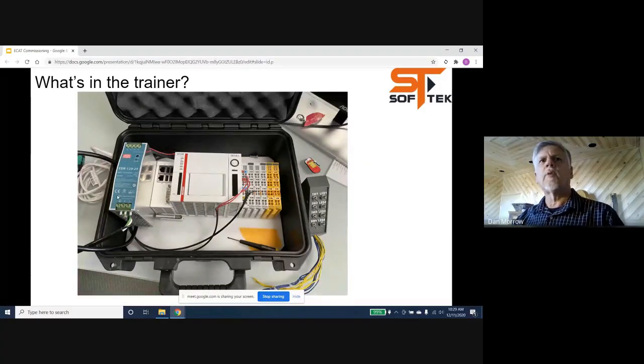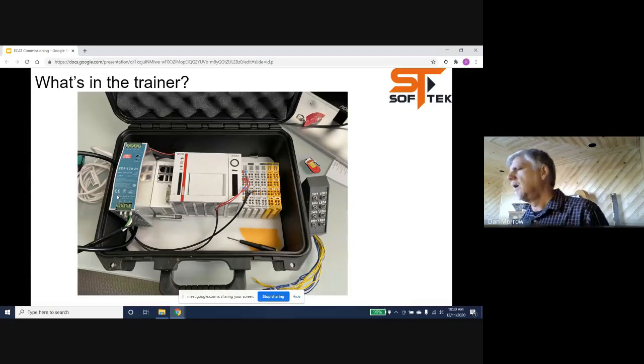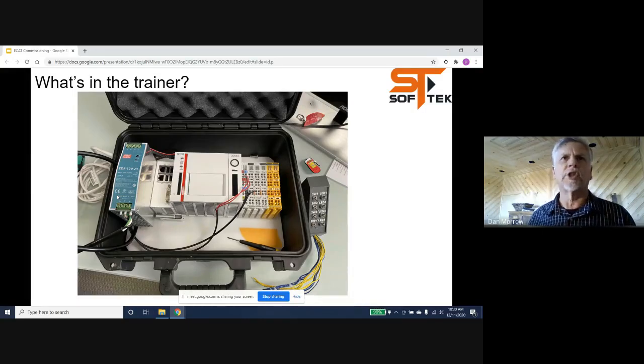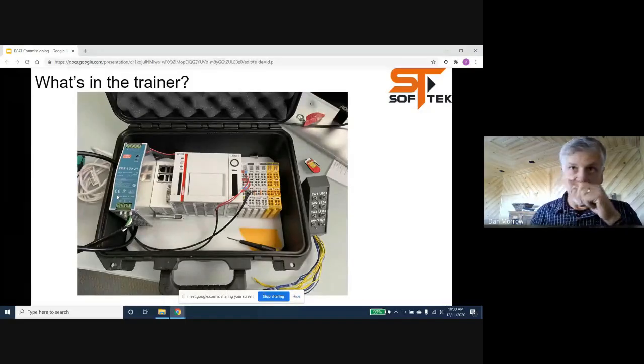So, 24-volt power supply. The EtherCAT systems use a 24-volt power supply, and there are two parts in the architecture. One part runs the EtherCAT bus and associated logic, the actual signaling. The other 24-volt runs all of the I/O on the slices. Then there might be a third power supply that supplies power to high amperage devices like motor drives, and sometimes you'll see a 48-volt supply dedicated to running one of those kinds of devices.